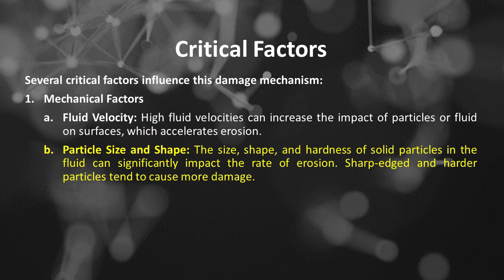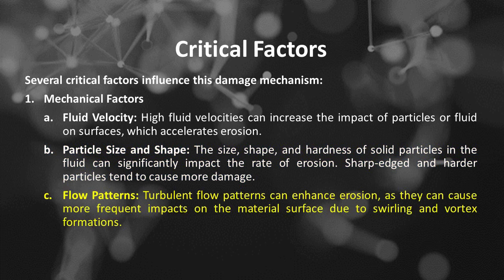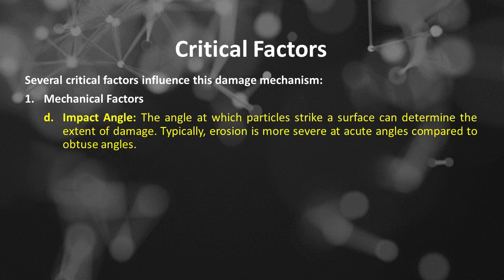The second is particle size and shape. The size, shape, and hardness of solid particles in the fluid can significantly impact the rate of erosion. Sharp-edged and harder particles tend to cause more damage. The third is flow patterns. Turbulent flow patterns can enhance erosion, as they can cause more frequent impacts on the material surface due to swirling and vortex formations. The fourth is impact angle. The angle at which particles strike a surface can determine the extent of damage. Typically, erosion is more severe at acute angles compared to obtuse angles.